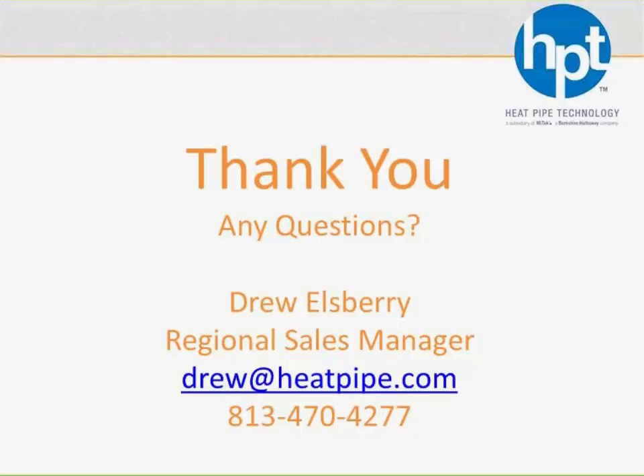Yes. Thank you, Maz. Last question I have is, where does the airflow distribution within a school typically create imbalance in comfort as far as temperature and humidity is concerned in a decoupled system? Well, most times when I see schools and when it comes to a decoupled system, typically that decoupled outside air is being distributed directly to the classrooms, and then the classrooms either have like a fan coil unit handling the sensible load in the space, and typically that DOAS air is being provided at near neutral air conditions or maybe slightly colder to somewhat aid in that sensible cooling.